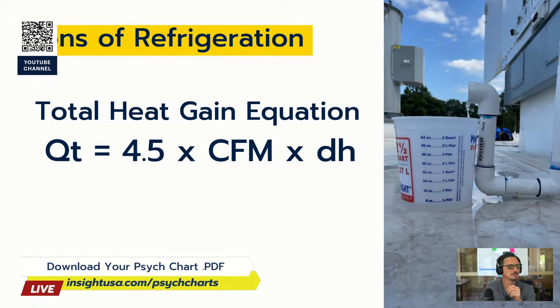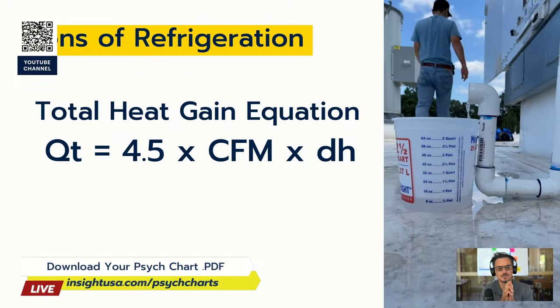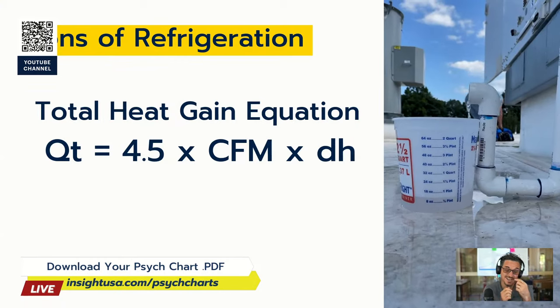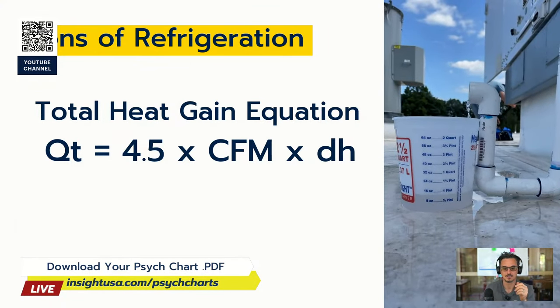QT is what I meant to say. So the total BTUs, total heat gain, equals 4.5, and that's another one of those that's not a constant, times CFM, cubic feet per minute, times delta H. Hey, what's this H thing? It's new. We're going to talk about that. That's enthalpy. So that's important to know as well.